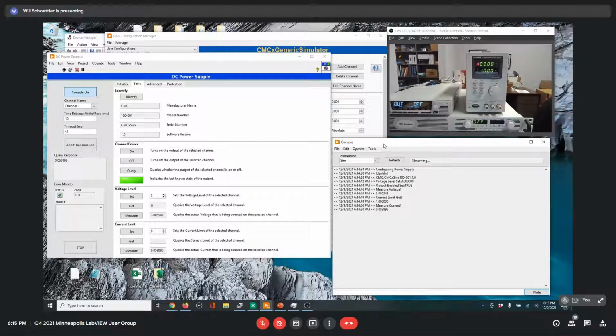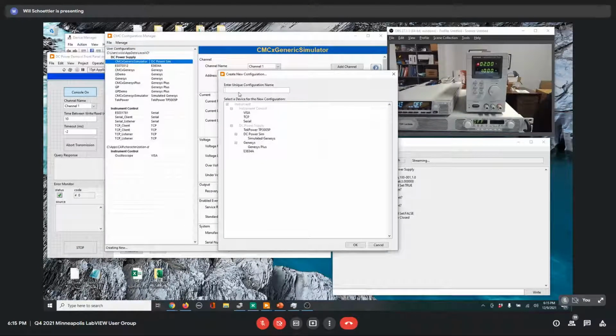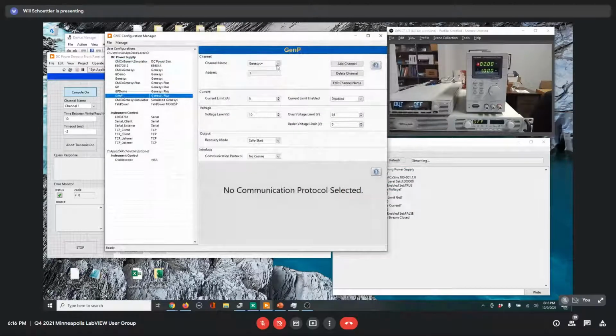Also, maybe we were using LAN connection on the Genesys, but we found out that we're getting network outages, so maybe we have to move back to serial. So similarly, it's just as easy to move to the Genesys Plus. We can just create our new, let's call it Gen P. Use channel 6 again.